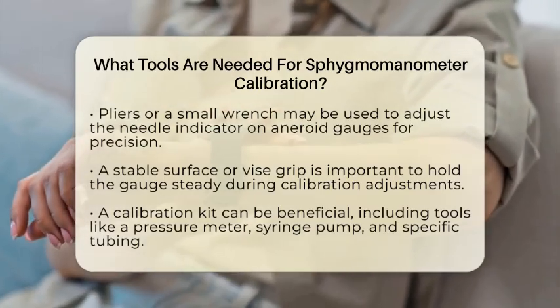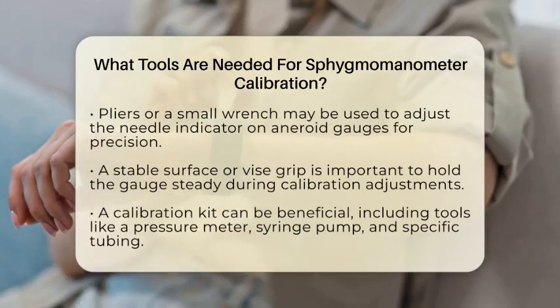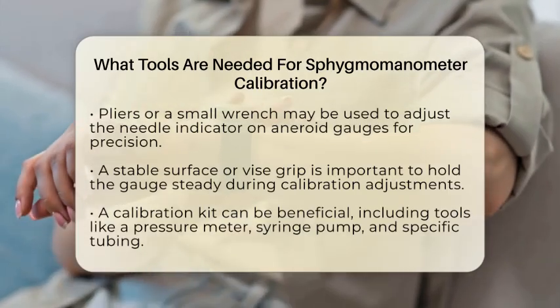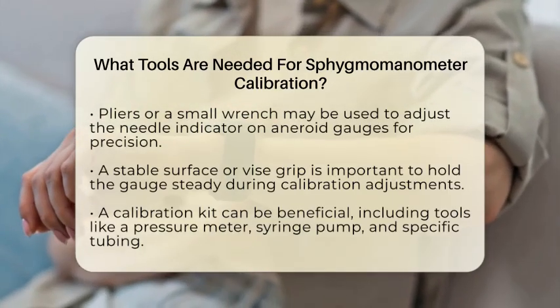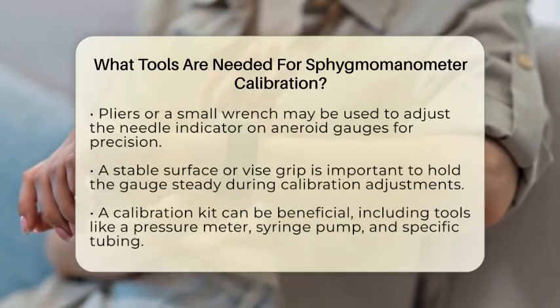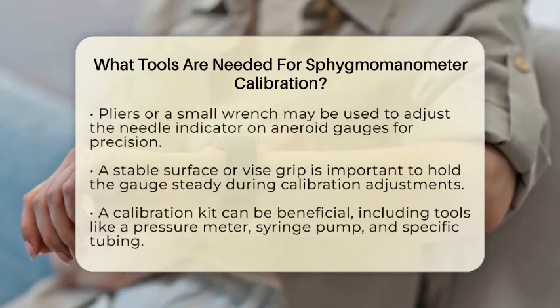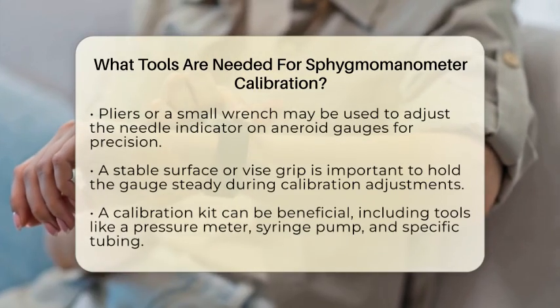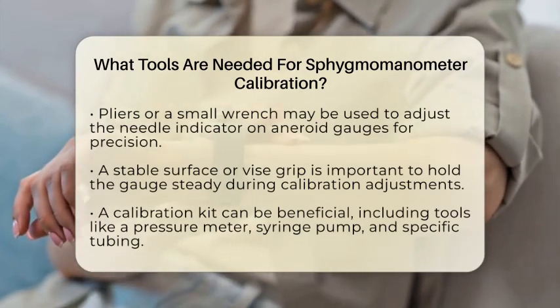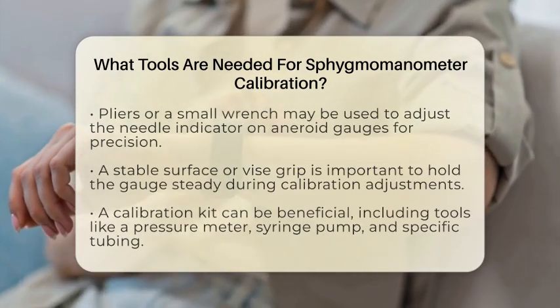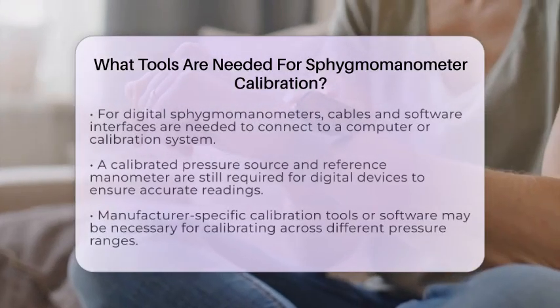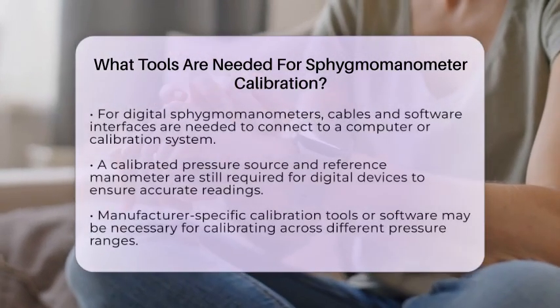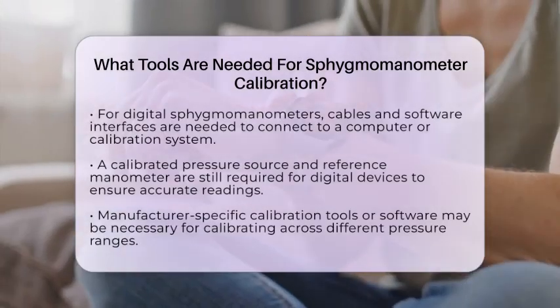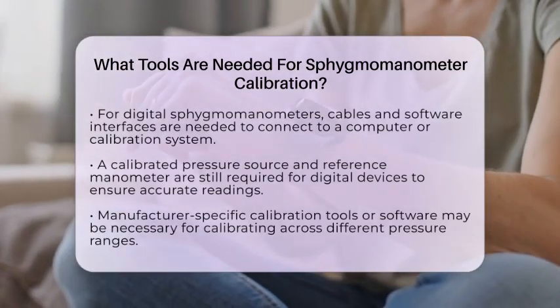A stable surface or a vice grip is also important. This helps hold the gauge steady during adjustments, preventing any movement that could affect the calibration process. While not mandatory, a calibration kit can be quite helpful. This kit may include a pressure meter, syringe pump, and tubing specifically designed for blood pressure device calibration. Having these tools can make the process smoother.